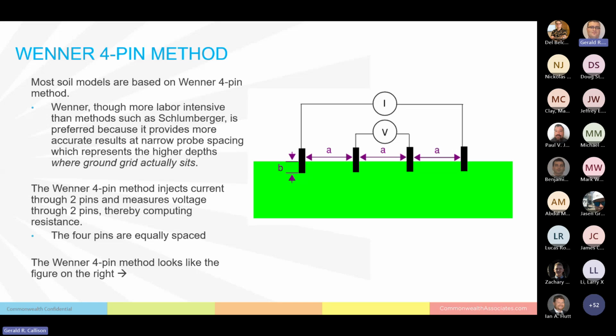Now, the Wenner 4-pin test is very important. You'll hear a lot about it. This is how we measure the resistivity of the soil and come up with the model we use in grounding. There are multiple tests by which to measure resistivity, but we use Wenner 4-pin. Some, like Schlumberger, are much less labor intensive, since you don't have to move all of the pins between tests. But the Wenner is used because it provides better, more accurate results for resistivity at more shallow depths of the soil.